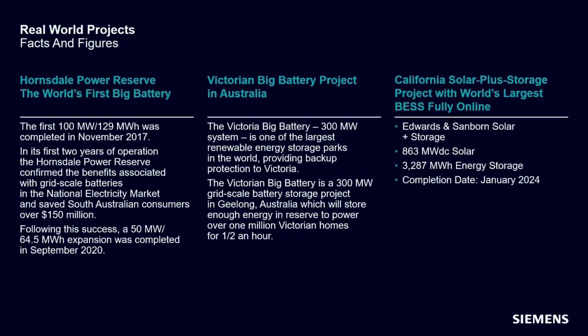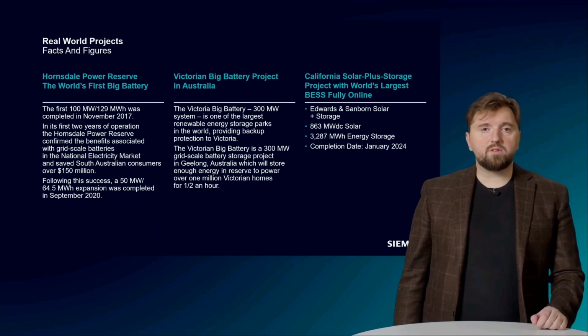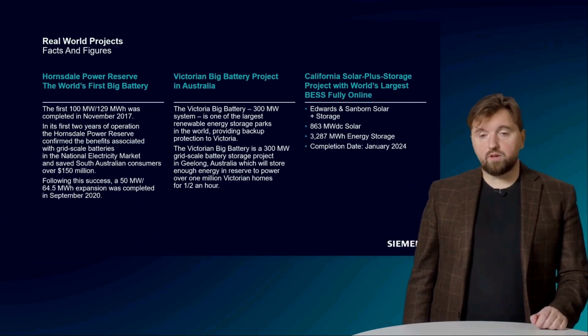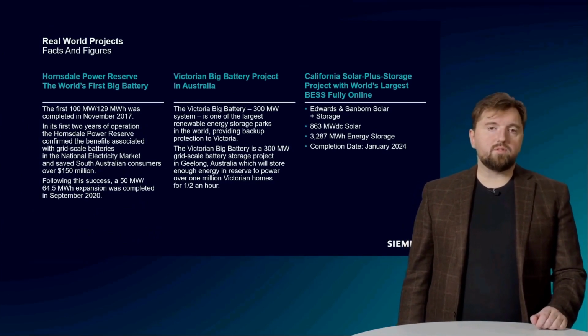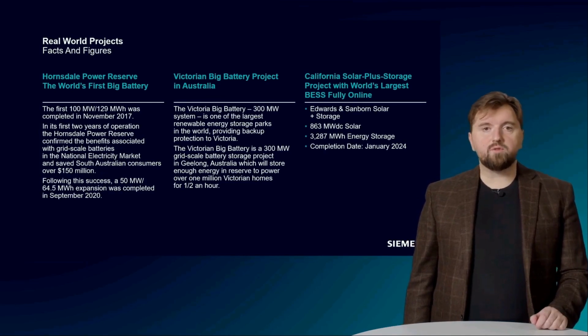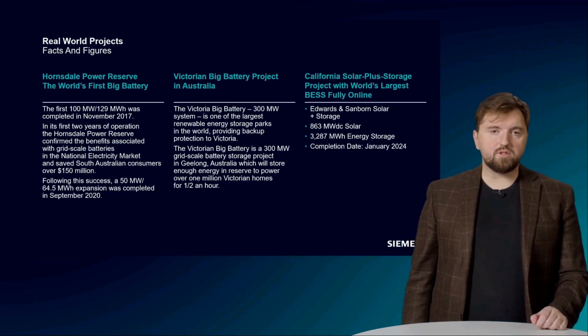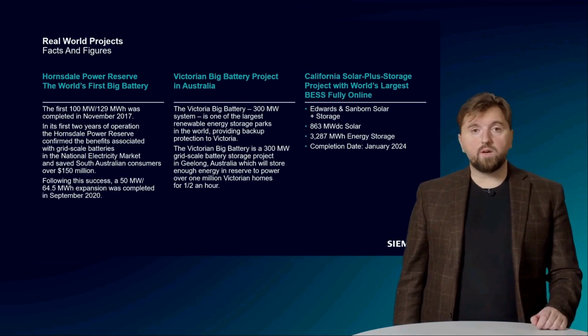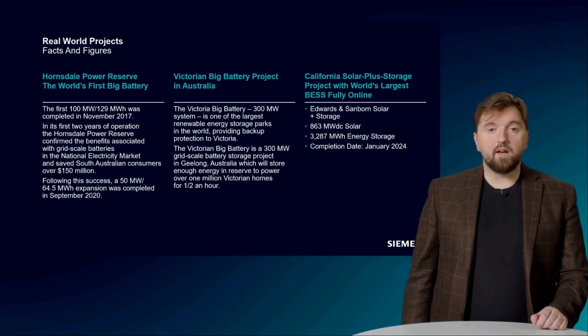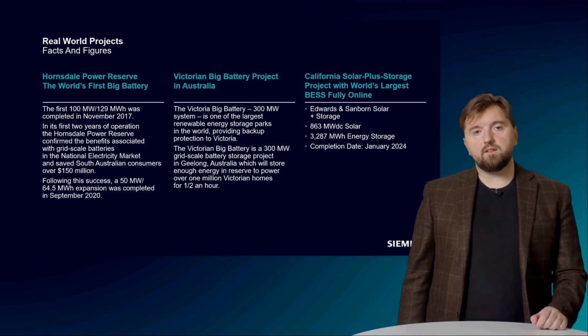Just in recent months, what claims to be the largest online BESS in the world is located in California as part of a solar plus storage project with an approximate battery size of 750 megawatt. The total battery capacity is over 3,000 megawatt hours. However, a large number of BESS projects are either under construction or have just been announced worldwide. It's just a matter of time before these BESS will no longer be considered the largest. In Germany, plans for a 1 gigawatt battery are already underway, and multi-gigawatt BESS are expected in the near future.